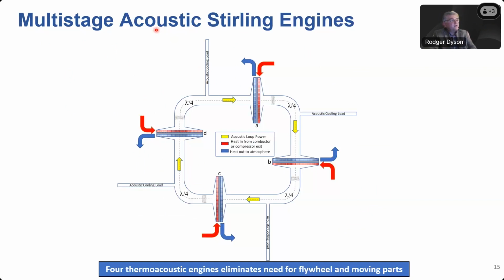With thermoacoustics, you can do the same thing but get rid of all the moving parts. All we have is a hot heat exchanger and a cold heat exchanger. Thermoacoustics is a field in which, if you have a hot area and a cold area, it'll amplify a sound wave. As the sound wave travels through the tube it gets amplified, travels around, gets amplified again, and reaches a peak based on the size of the heat exchangers. Because we have 4 of them, all 90 degrees apart, we don't need a resonator or flywheels, very similar to the 4-piston engine I showed, which shrinks the size down significantly.